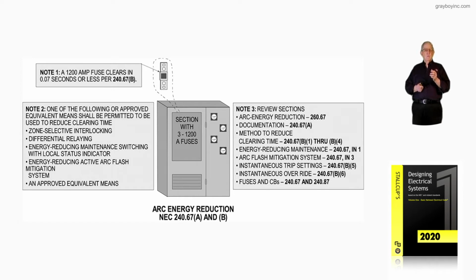Now, notice in note 2, we're getting the same benefit that we had with a circuit breaker. But now, I won't go over that again, but notice to the right, we have the note 3, and notice that to really get a good handle on what type of protection we have here using the arc energy reduction. Now, notice fuses, they actually can clear fast. But most of the time when we use circuit breaker type action, what we're doing is just energy reduction type equipment. That is usually what you're dealing with there.